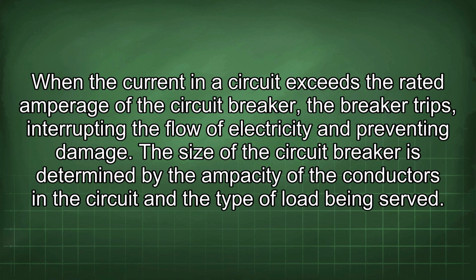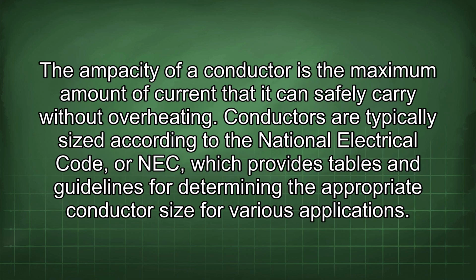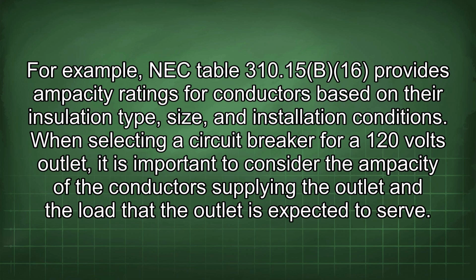The size of the circuit breaker is determined by the ampacity of the conductors in the circuit and the type of load being served. The ampacity of a conductor is the maximum amount of current that it can safely carry without overheating. Conductors are typically sized according to the National Electrical Code, or NEC, which provides tables and guidelines for determining the appropriate conductor size for various applications. For example, NEC Table 310.15(B)(16) provides ampacity ratings for conductors based on their insulation type, size, and installation conditions.